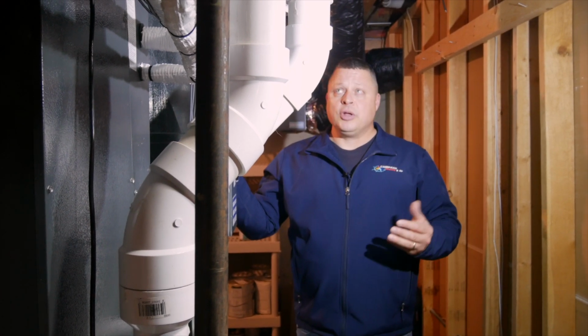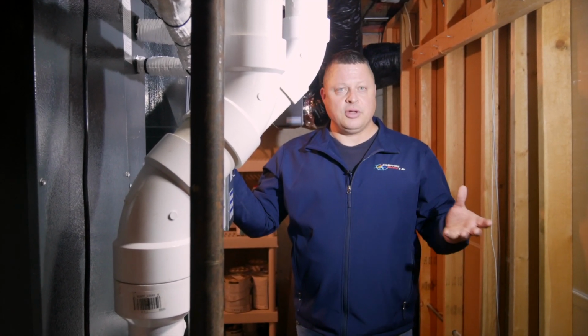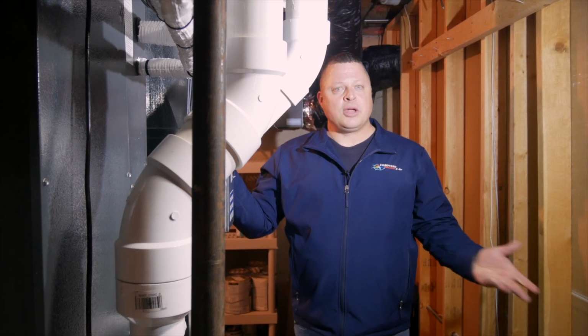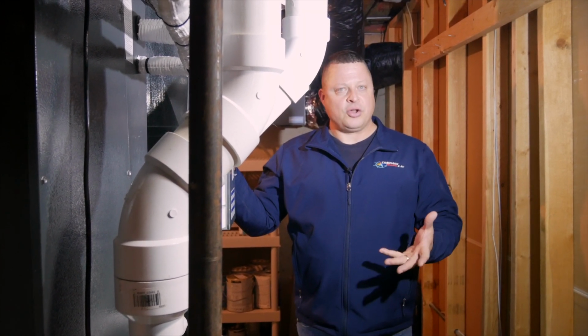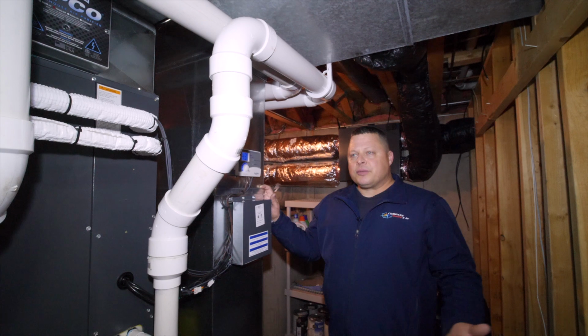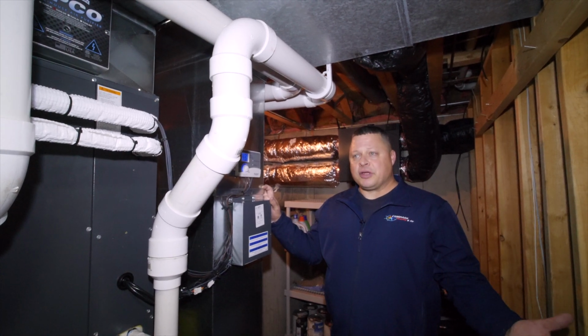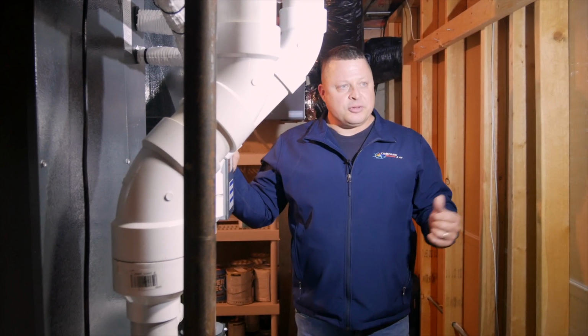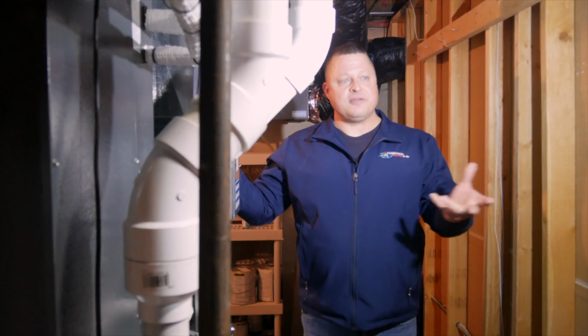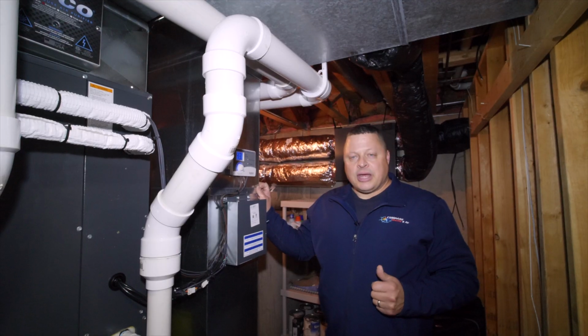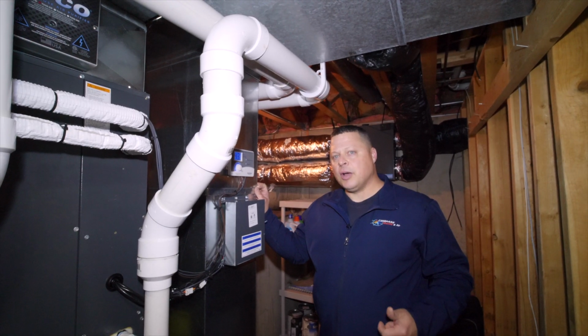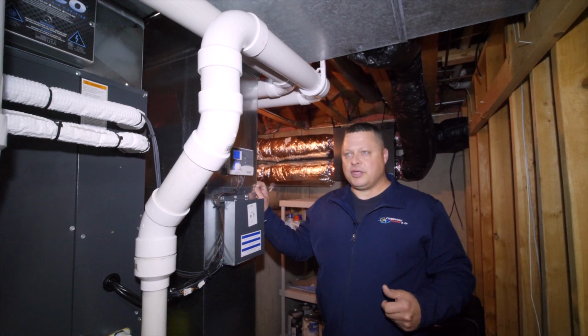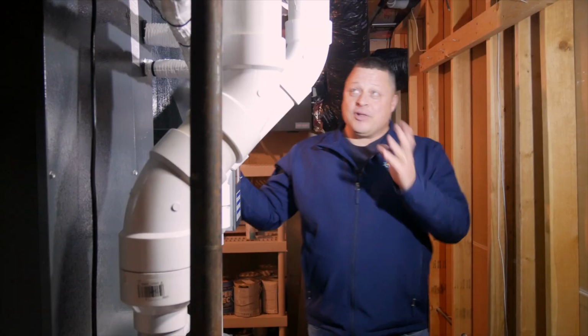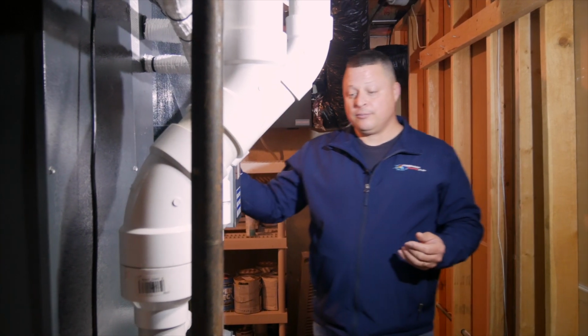Another benefit to a UV in general, on the UVC, is they eliminate your VOCs, your volatile organic compounds. That's the number one reason that you have formicary corrosion. What formicary corrosion is, is little pinholes that you'll get in copper tubing. So a lot of the coils that wind up with leaks, stuff like that, that is caused by the VOCs in the home. The UVC light helps to eliminate that because of the ability to get rid of those VOCs. So that's the UVC system.